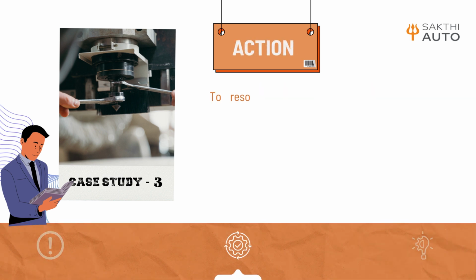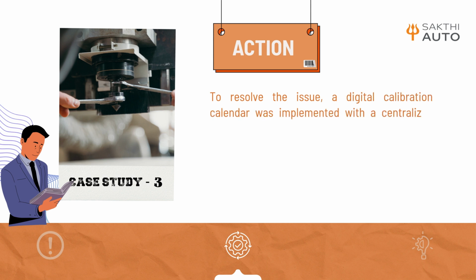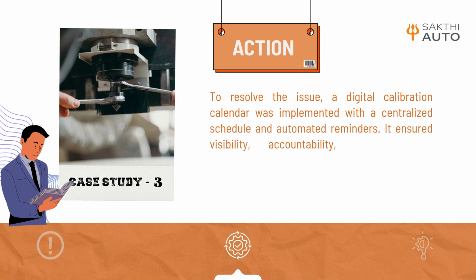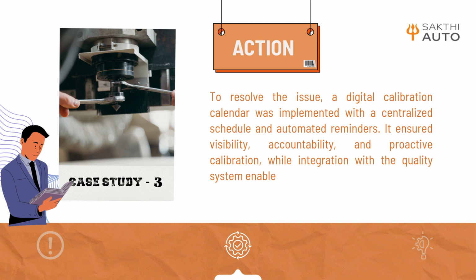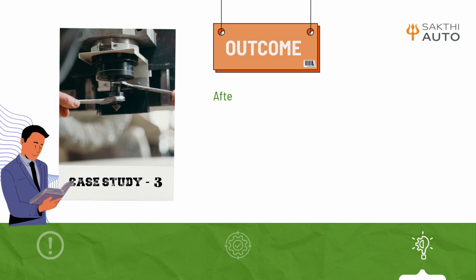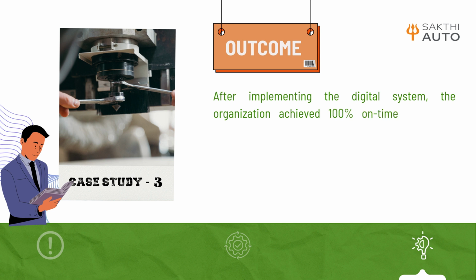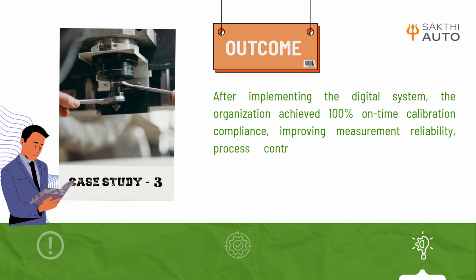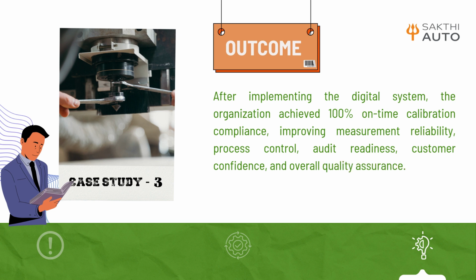Action. To resolve the issue, a digital calibration calendar was implemented with a centralized schedule and automated reminders. It ensured visibility, accountability, and proactive calibration, while integration with the quality system enabled easy tracking during audits. Outcome. After implementing the digital system, the organization achieved 100% on-time calibration compliance, improving measurement reliability, process control, audit readiness, customer confidence, and overall quality assurance.